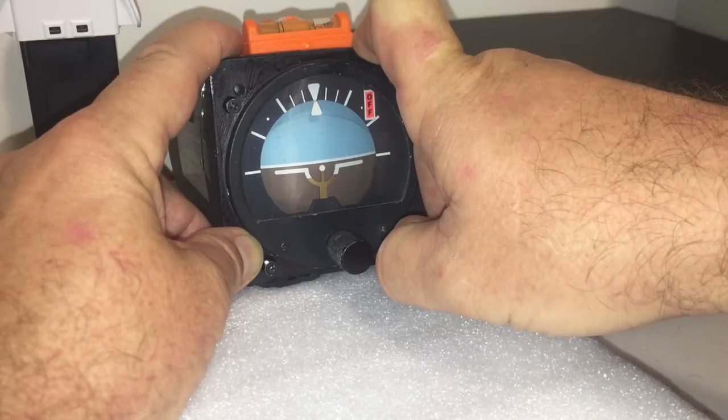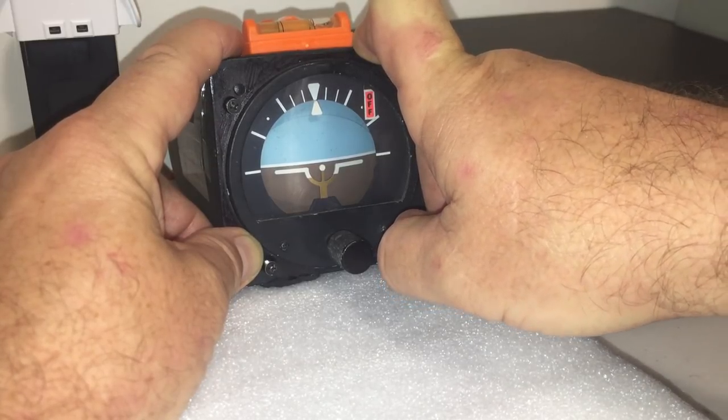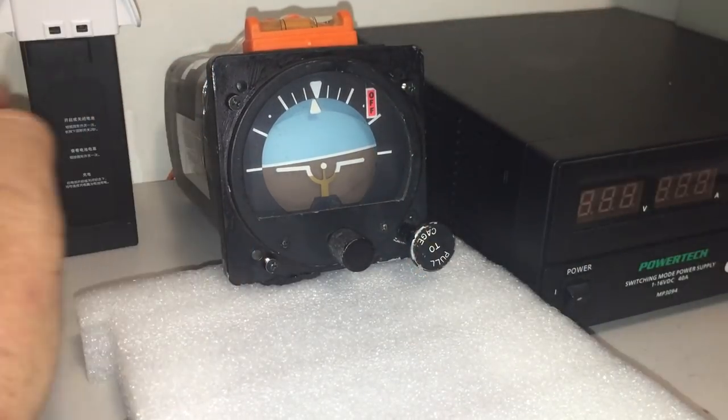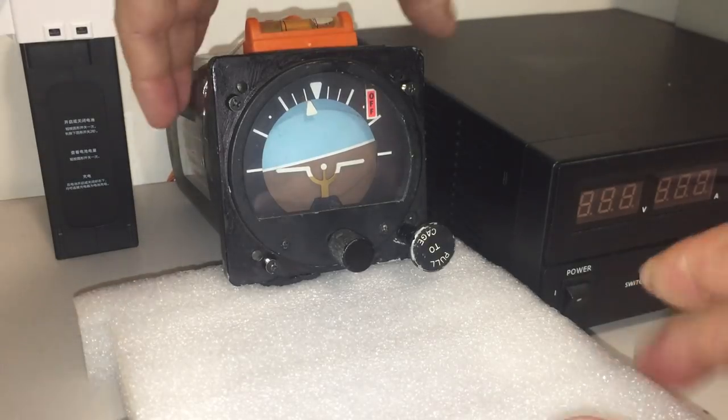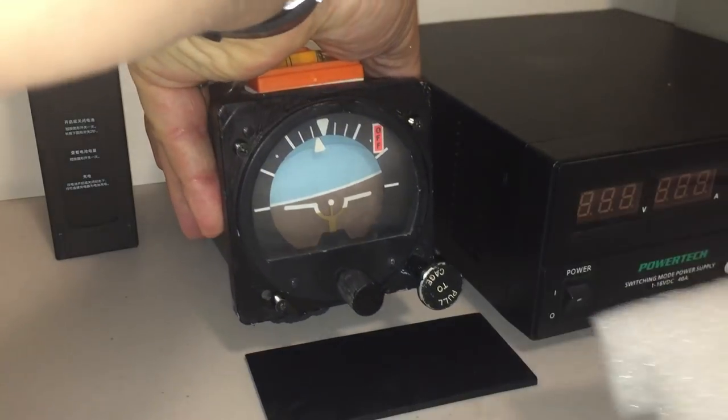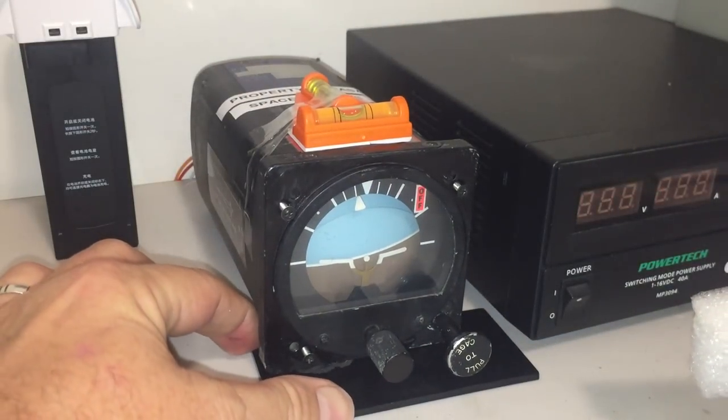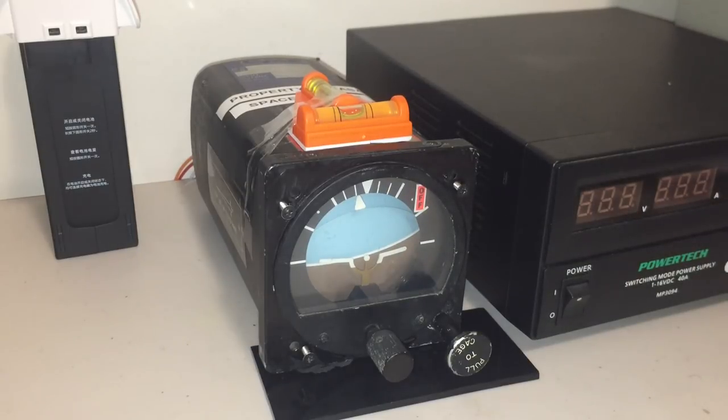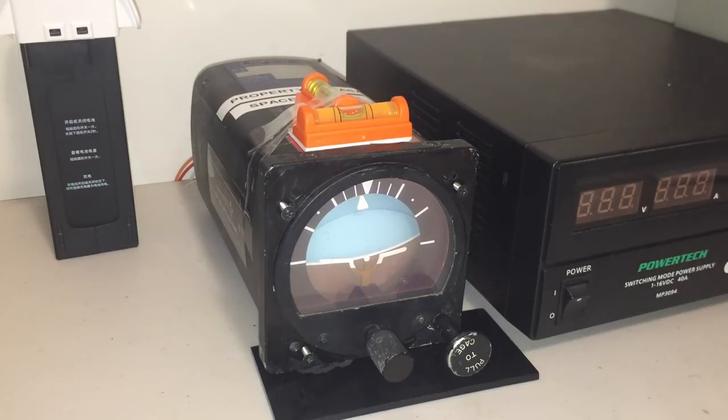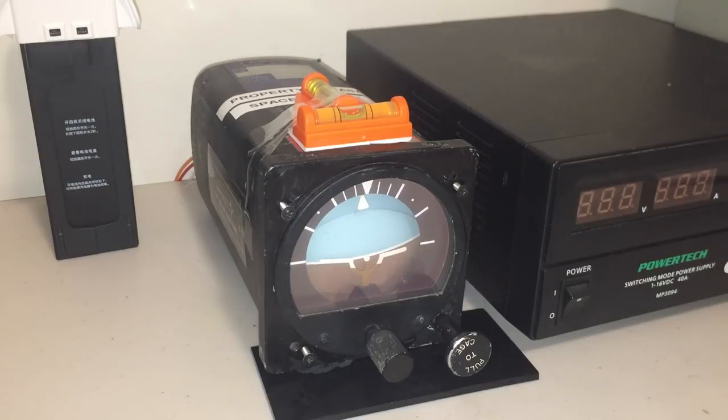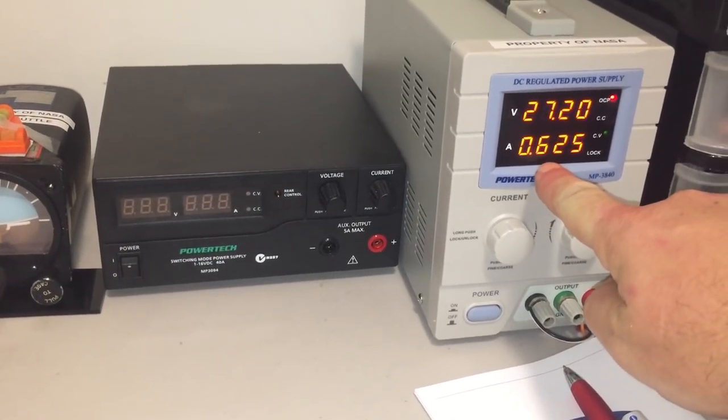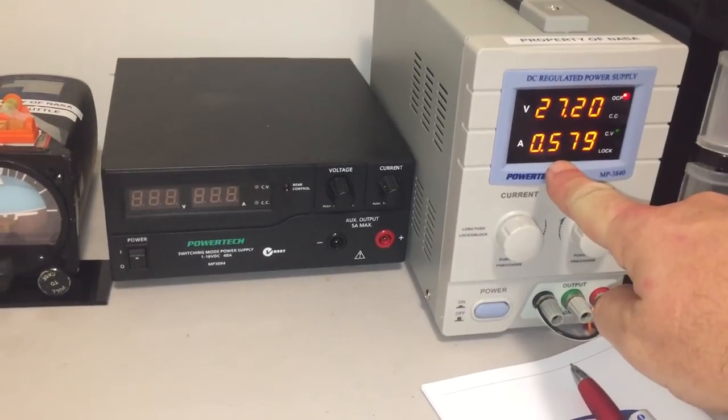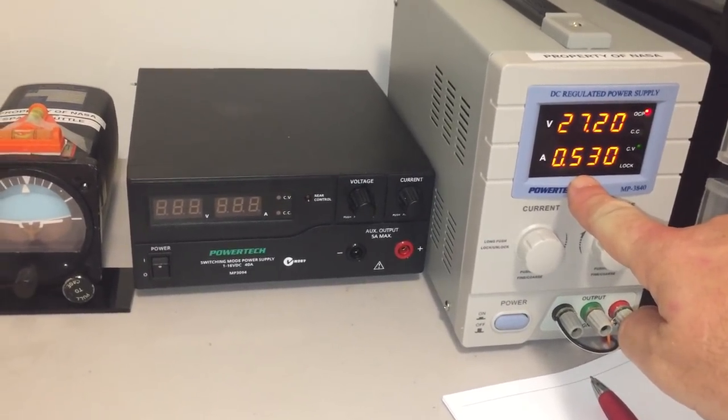Okay, I'm fairly happy the gyro has completely stopped, so I'll now release the cage. And what I'll do is return the gyro to the level it was originally and repower the gyro. And you can see while it's powering up, the current draw is higher than half an amp. When it gets up to the correct operating speed, it's less than half an amp.